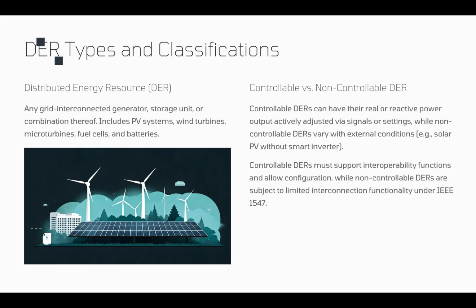Now, the other class is non-controllable DERs. From the name, you can expect that these are the DERs that cannot adjust output in response to any external commands. They operate independently, based on the local environmental conditions and their internal settings. It could be a basic rooftop solar, or a small wind turbine with a fixed-speed induction generator. Because those non-controllable DERs have limited interconnection functionality, they only need to meet basic requirements like anti-islanding, trip and reconnect requirements, or harmonic distortion requirements, because they cannot participate in active grid support functions.